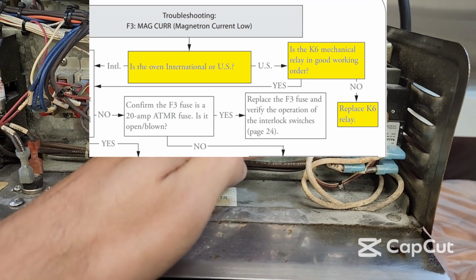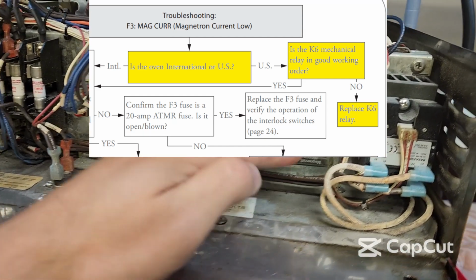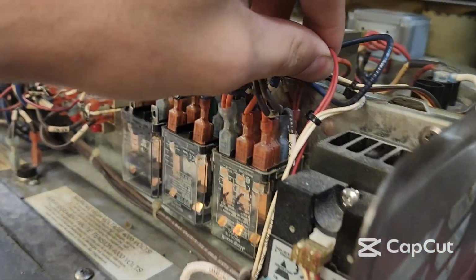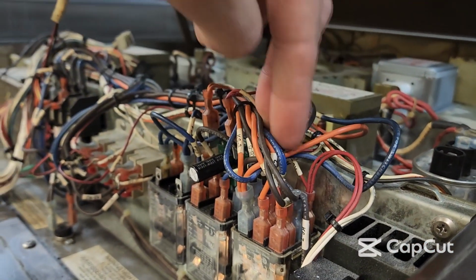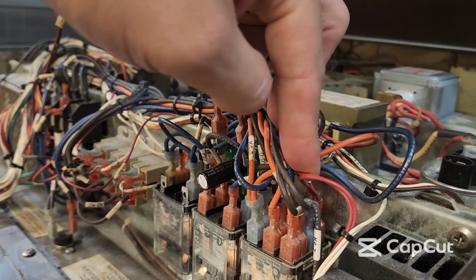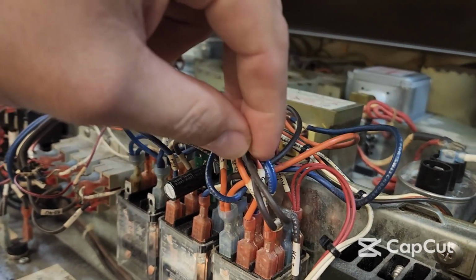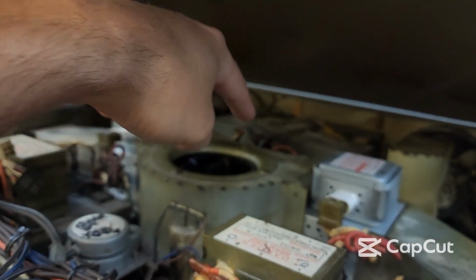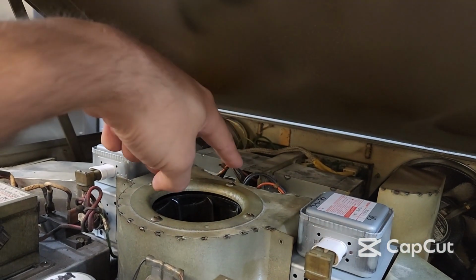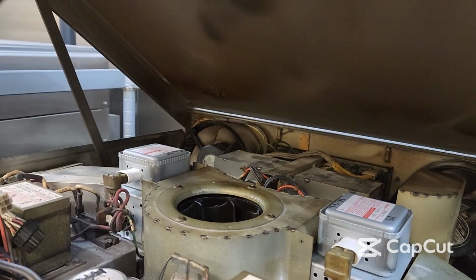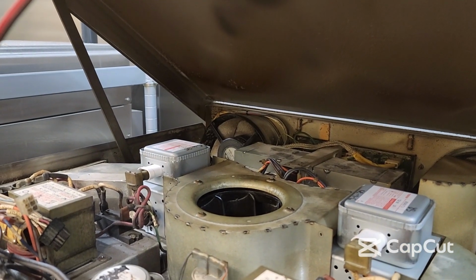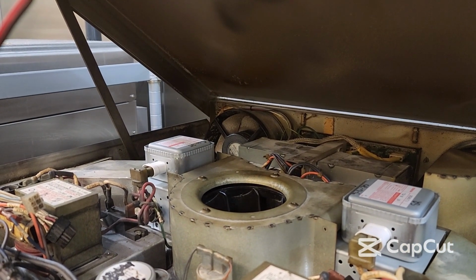You can verify the K6 is getting signal by testing your signal wires, which are going to be in the back, which are always in the back, so you have to unplug them, and then you'll actually have to try to get that activated to see that. Or you can test your primary voltage coming in and make sure that when you have 208, you're getting 208 and it's not going to the 240 volt tap.